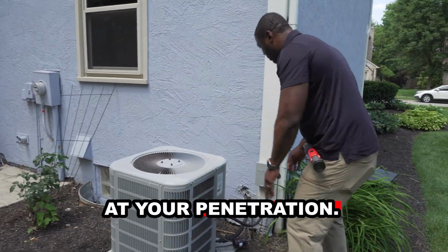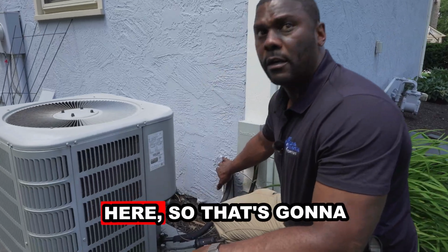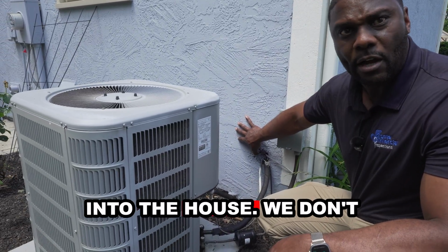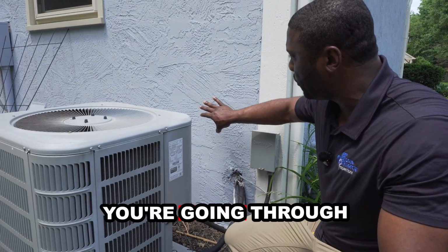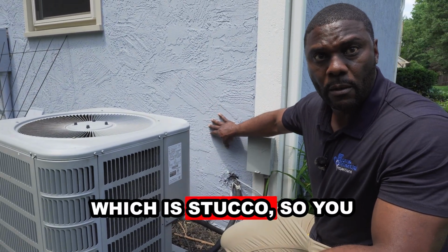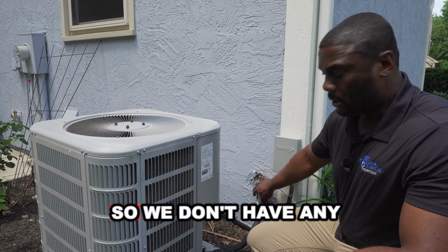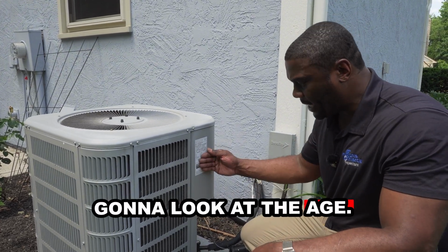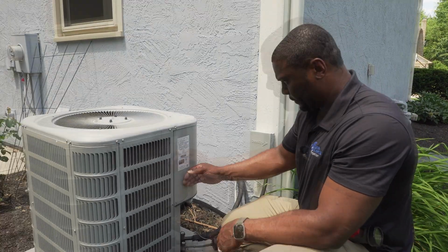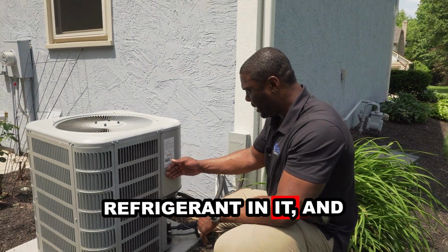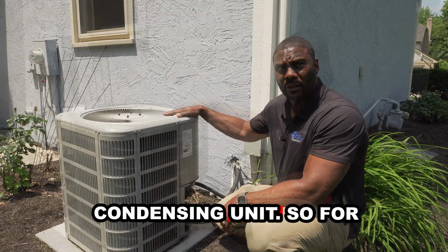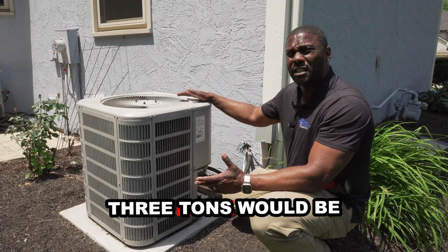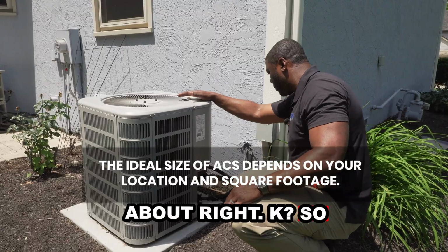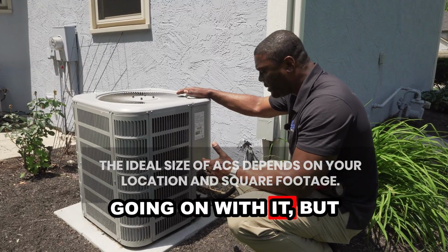You always want to look at your penetration. We got some spray foam here, so that's going to allow for water to get into the house. We don't have a good penetration. Plus you're going through masonry, which is stucco. So you always want to have conduit. So we don't have any conduit here, so we're going to look at the age. This is a 2019. It's got R410A refrigerant in it, and it's a 3-ton condensing unit. So for this size of house, 3 tons would be about right, okay? So really not seeing much going on with it, but we're going to use our thermal camera on the inside to see if we're getting a good temperature differential and inspect the units.